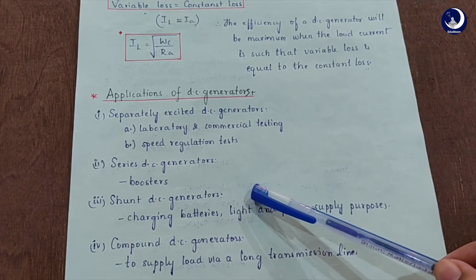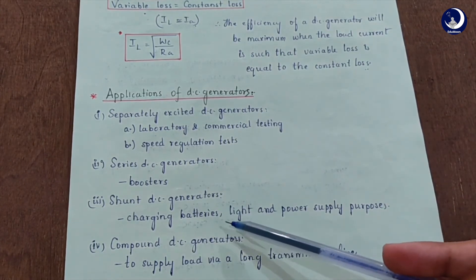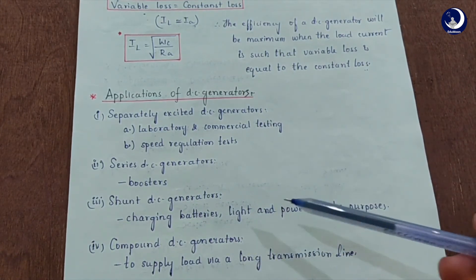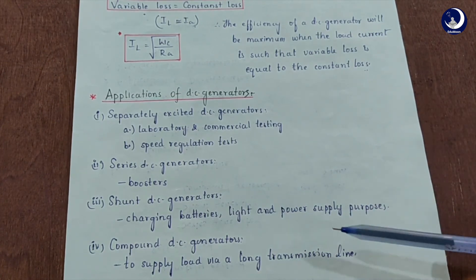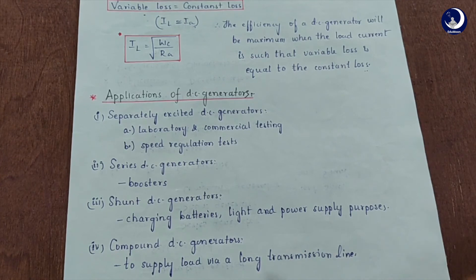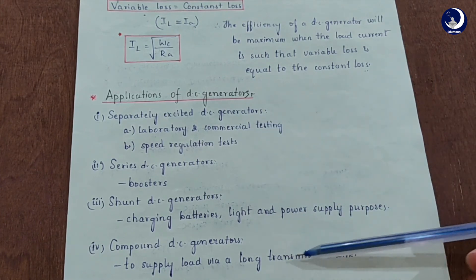The shunt DC generator essentially maintains a constant terminal voltage, so it is used for charging batteries. Shunt generators with field regulators are generally used for light and power supply purposes. The over-compounded DC generator is used where the generator is required to supply load via a long transmission line, because over-compounding compensates for the voltage drop in the line, maintaining constant voltage at the consumer's terminals.